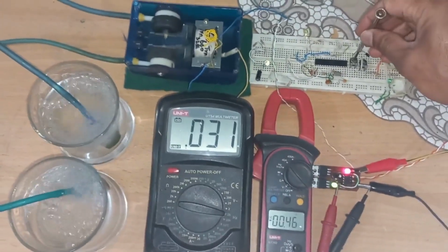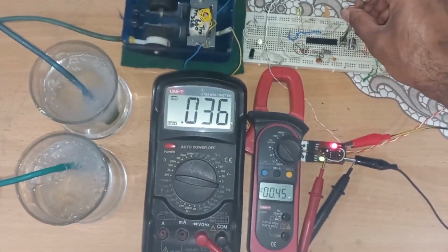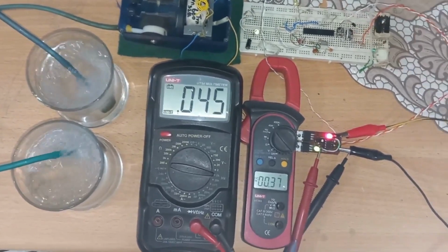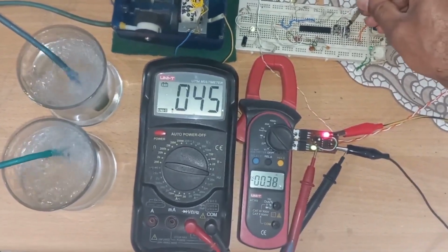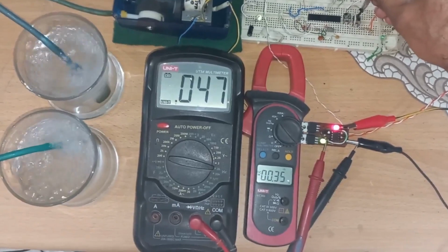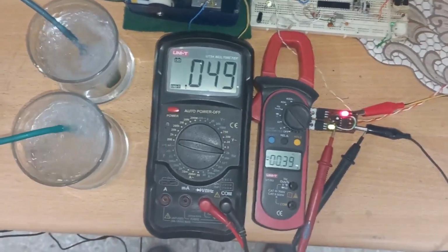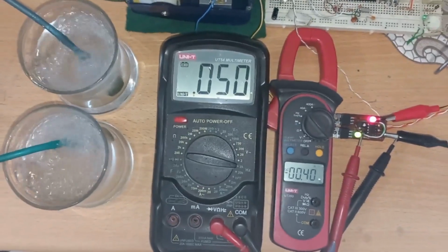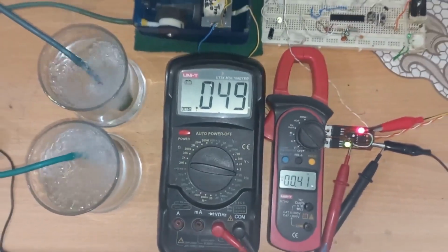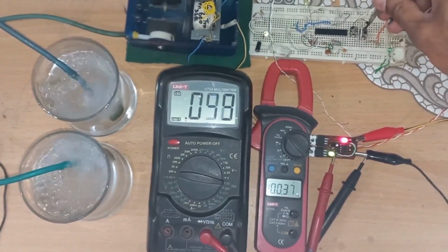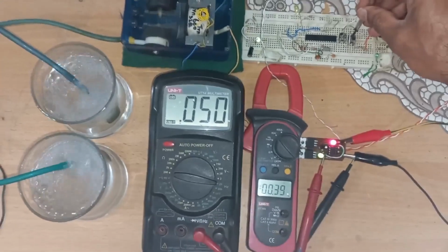So I will increase the frequency again, 45, and with the second potentiometer. Now if I increase the frequency till 49 Hz, its maximum frequency and maximum air pressure, the current came back to 0.4 or 0.38. Now if I increase the frequency a little bit more, then we see what will happen.